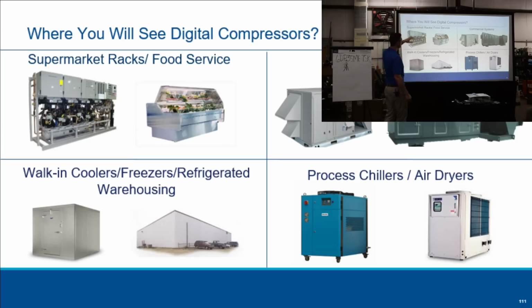Different types of solutions: supermarket racks, walk-in freezer, commercial system. One thing about the digital compressors though, they're not for every application. They're not very efficient at part load. Okay? So you have to think about that. And what was your name? Chris. Chris mentioned that they're very loud. So if you take a digital compressor and put it on a metal roof right above the boss's office, he's not going to be too happy. So you have to think about where you're putting the digital compressor. Okay? So it's not for every application, but it can fit a lot of applications.